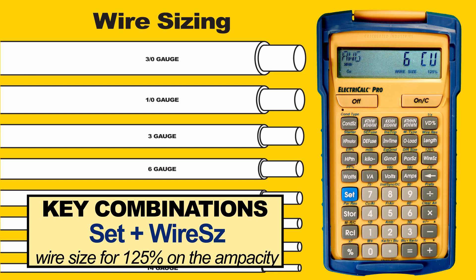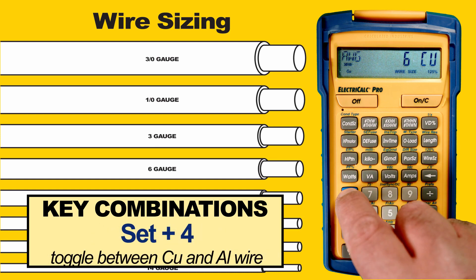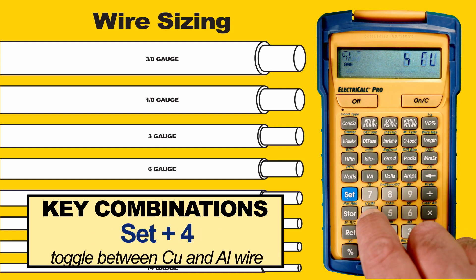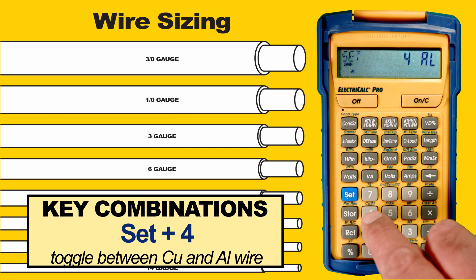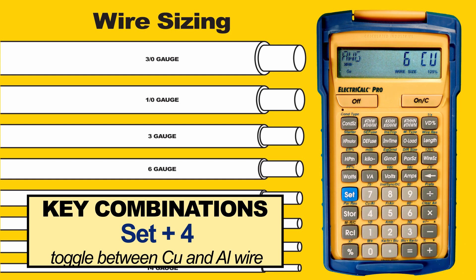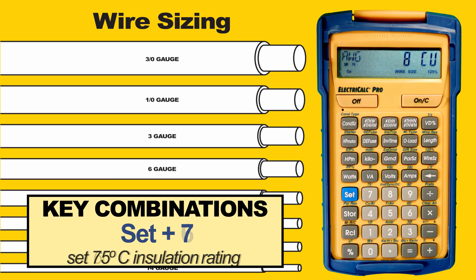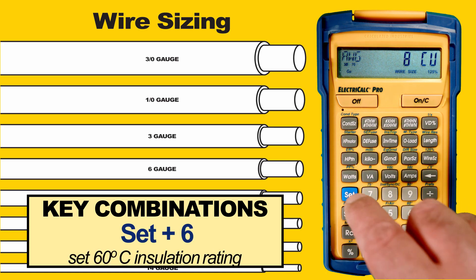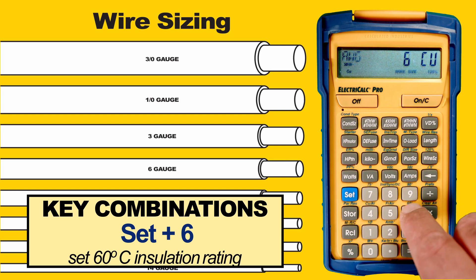We can also change the wire type. Press Set to select the second function of the next key we press, then press 4. We see that the function is a toggle between copper wire and aluminum wire — let's set this back to copper wire. We can also change out of the default 60°C insulation rating by pressing Set for the second function, then 7 for 75°C, Set then 6 for 60°C, or Set then 9 for 90°C.